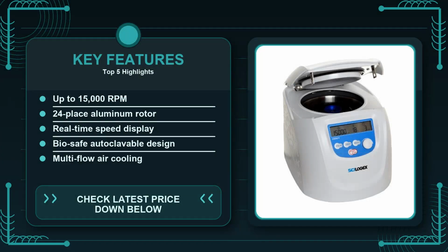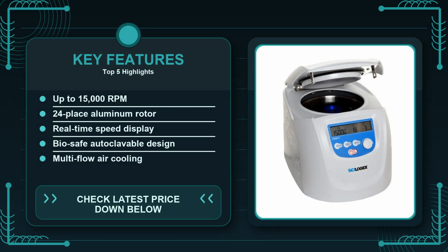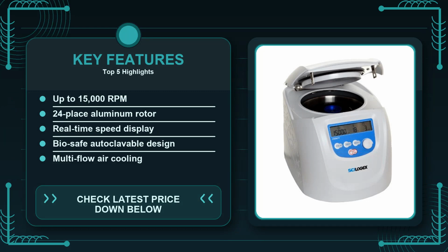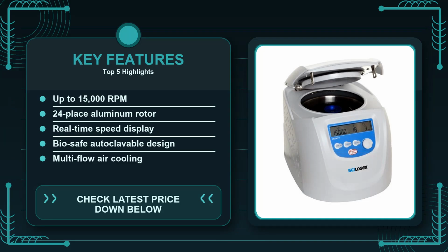Safety is another area where the SCI 24 tries to differentiate itself. The rotor is labeled biosafe and can be autoclaved, which is a real boon if you're working with pathogens or sterile samples. You can place the rotor directly into the autoclave without worrying about degrading the balance or the sealing surfaces. The unit also has an interlock that prevents the lid from opening while the rotor is still moving, and the digital readout won't let you start a spin unless the lid is fully closed. In practice, this means you can trust the machine to keep your samples sealed, and you avoid the awkward stop the spin, then manually close the lid dance that older models sometimes force on you.